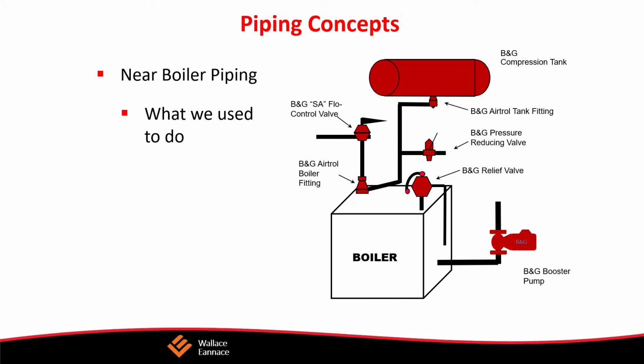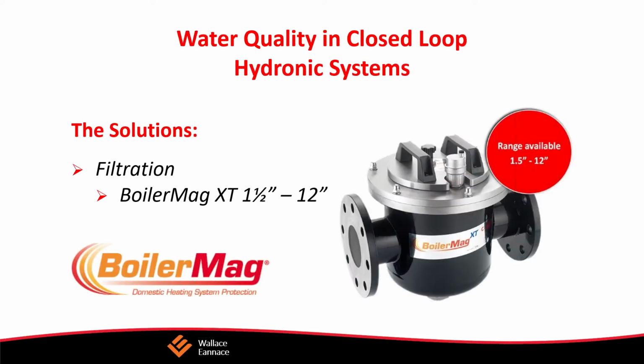Essentially, as heated water travels through iron systems, whether they be cast iron or iron pipe and the like, what'll happen is that magnetite, or small bits of iron oxide, will fall out of the system. If you've ever put in radiant systems, you put in those nice clear pipes, you come back 6 months later and there's black stuff all over the place. That is essentially the magnetite that has fallen out of the system.